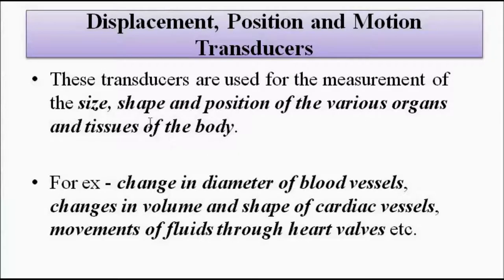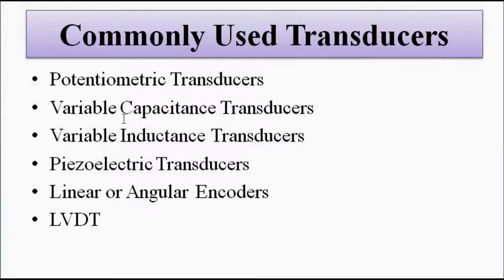Displacement, position, and motion transducers are particularly used for measurement of the size, shape, position, and movement of various organs and tissues in the human body — for example, changes in the diameter of blood vessels, changes in the volume and shape of cardiac vessels, and movement of blood and essential fluids through various organs. Commonly used transducers discussed so far include resistive/potentiometric, variable capacitance, inductive, piezoelectric, and linear variable differential transformer methods.